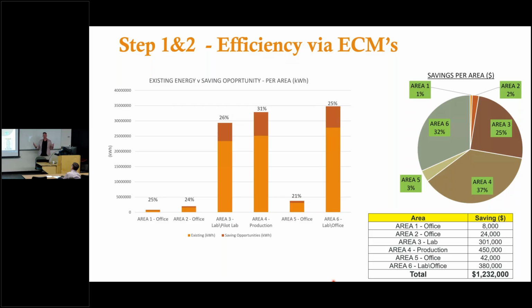Labs could be having 40 air changes per hour when a space only needs 8 air changes per hour. You could compromise down to 12. That's still a huge reduction. And those optimization opportunities end up benefiting the bottom line significantly. So when we're starting to talk about this, it just makes a lot of sense.